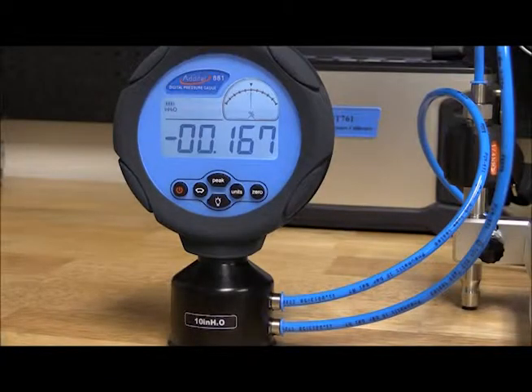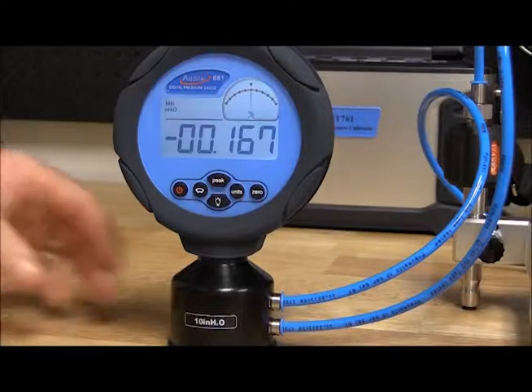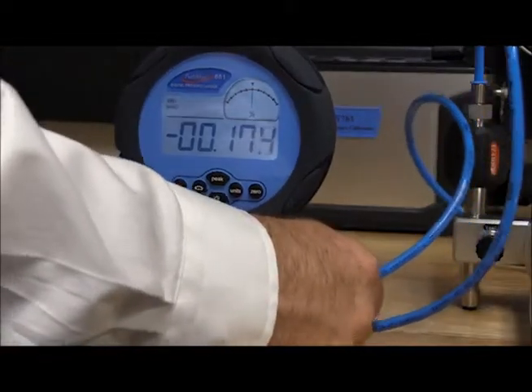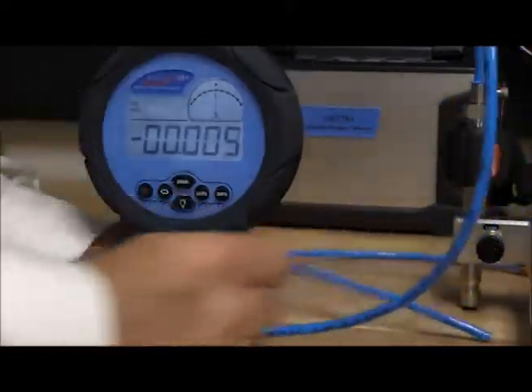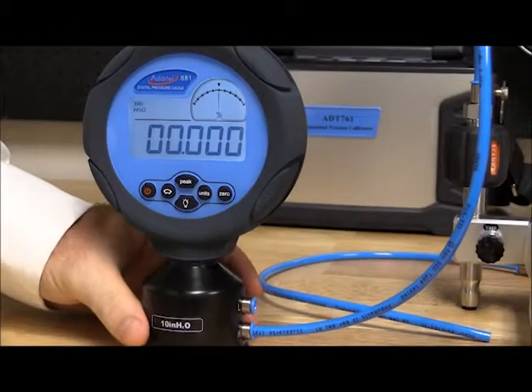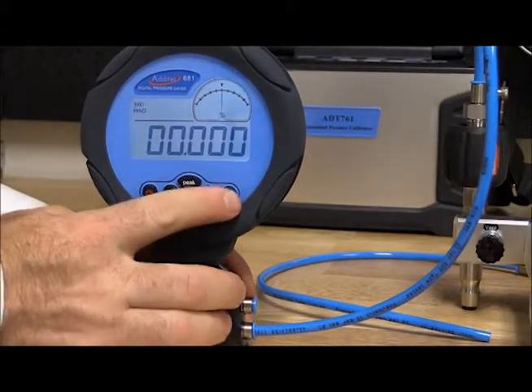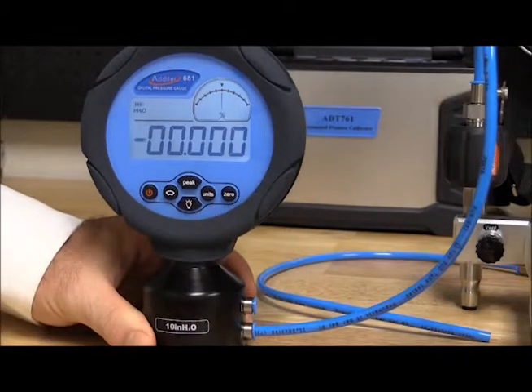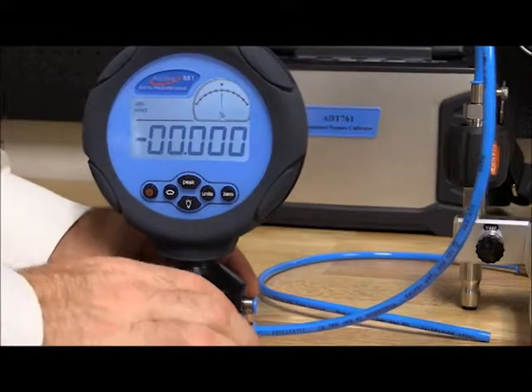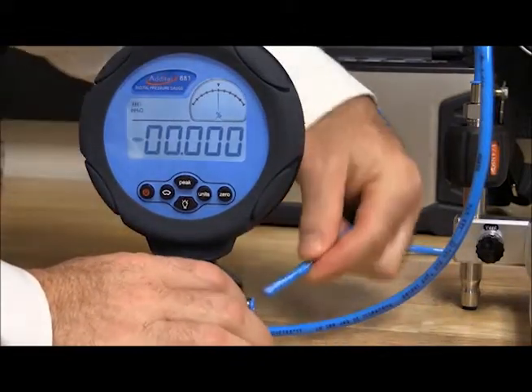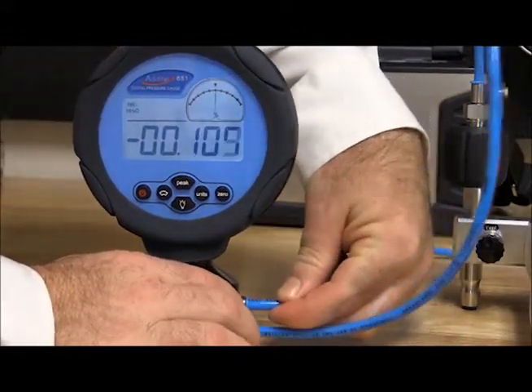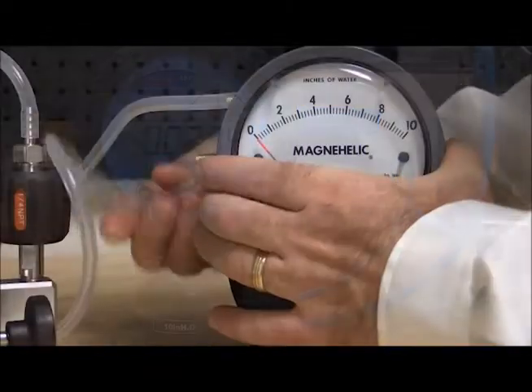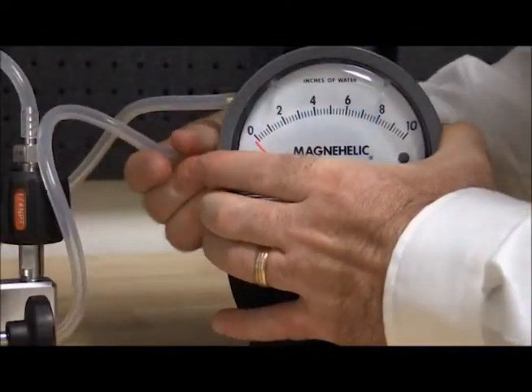Recording the zero point may vary depending on the type of DUT. If the DUT is a digital gauge, then keep the reference gauge and the DUT reference ports connected together and zero both gauges. In this example, I have an analog gauge, so I will disconnect both the reference ports and leave them open to atmosphere to zero the 881 reference gauge. After recording the zero, we will connect both reference ports together and proceed through the calibration.